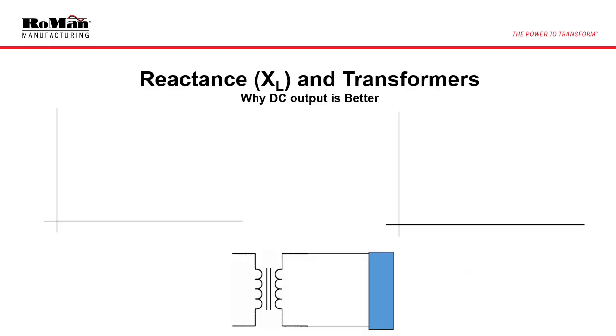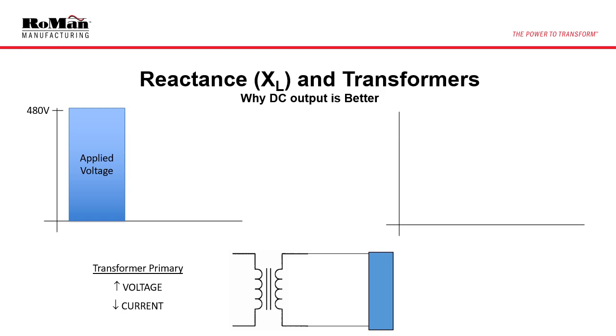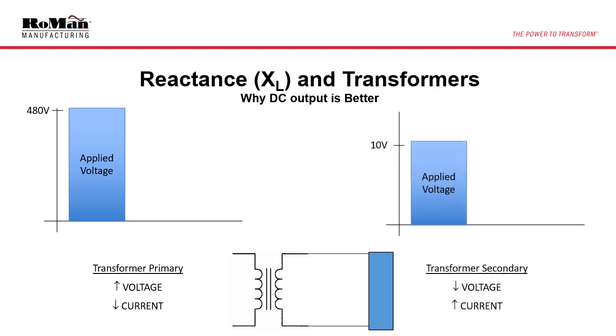Let's examine why a DC output is truly better. With a standard model, we will apply 480 volts to a transformer primary. This voltage can be stepped down to 10 volts, and you can see we have a low current primary and a high current secondary. At the transformer primary, an induced voltage is generated, which opposes the applied voltage. This induced voltage is a function of the magnitude of current change and has a relatively low impact because we have low current. Therefore, our usable voltage remains relatively high.